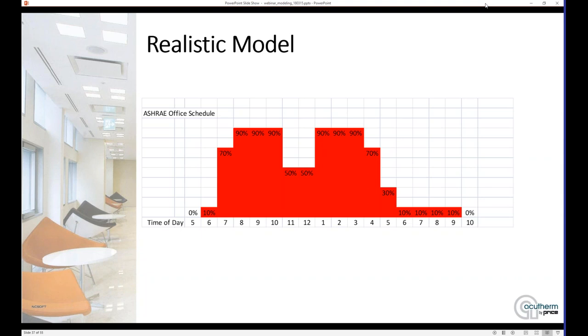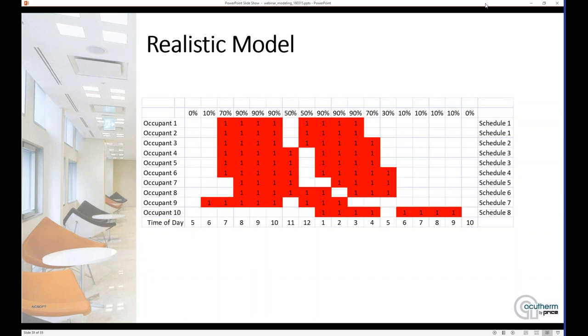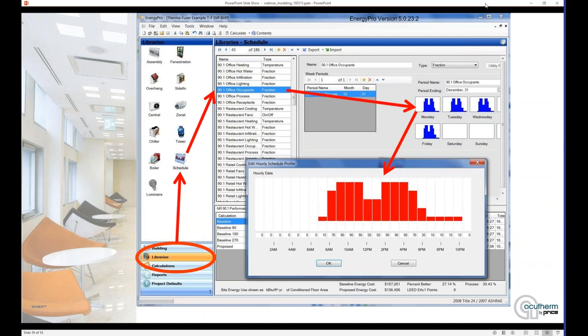For example, here's an office schedule — the ASHRAE office schedule. If we look at 9 o'clock in the morning, what they're saying is 90% of the offices are occupied. So instead of using 0.9 in every office, you can break that down. In this example, I created 10 occupancy schedules just to make the math easy. At 9 o'clock in the morning, 9 out of 10 people are in their offices, and the tenth office is unoccupied. With these 10 different occupancy schedules, you can randomly put them around the building and create that occupancy diversity that occurs in a real building as loads shift around as people come and go. The nice thing is you don't have to do this on every job — you can build a few of these and put them into your library, and then pull them out and insert them when it comes time to run a model.